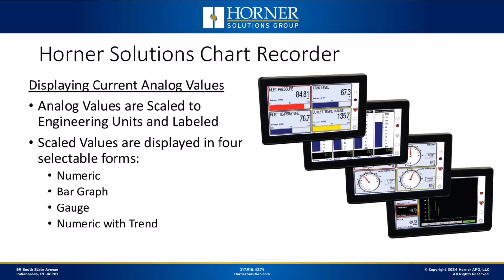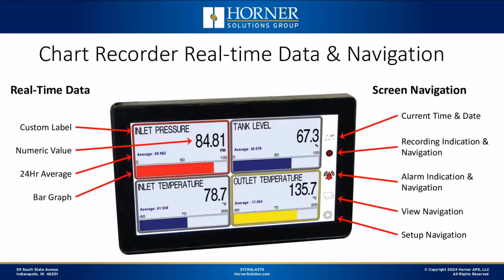Now, when it comes to displaying current values of the analog signals that are being monitored, basically what the unit does is it reads the analog inputs that are connected to the sensors in the field. It scales those values based on how the unit was configured from the touchscreen, and we'll review how that's done in a minute. And then it displays on the screen the process parameter in the engineering units in which you would like to display it. So whether that's pressure or PSI or temperature or whatever the case may be, that scaled value is displayed on the screen, and you can display it numerically, as a bar graph, in a gauge object, or again, on a trend object as well. So there's lots of ways that you can display the current value of that key process parameter that you're recording.